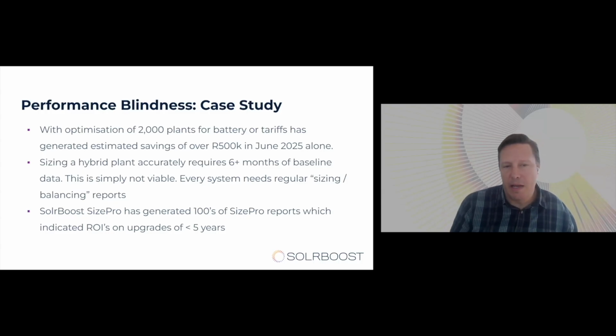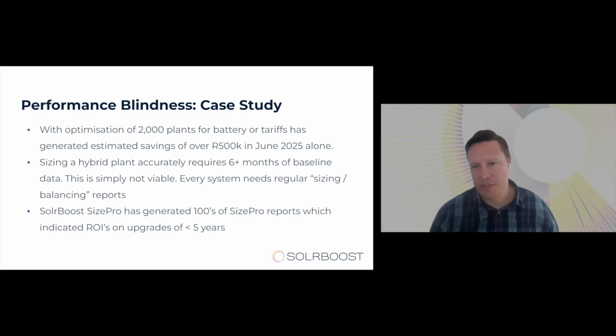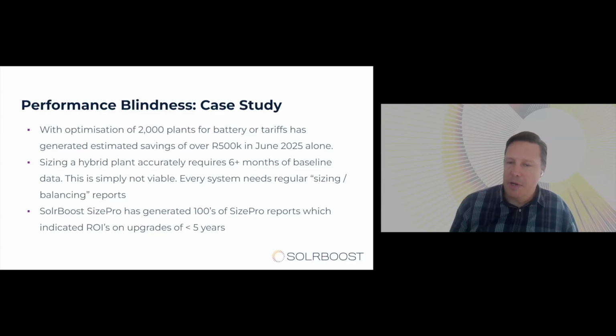Then, talking about balance or sizing of plants correctly, particularly in the residential and small CNI space, and probably even in the mid CNI space, the ability to size a system requires at least 6 months, ideally 12 months, of baseline data to understand how that site consumes electricity and what their load patterns are. But what's also important is that this changes over time. It's not a static thing which you've done once and it's correct.